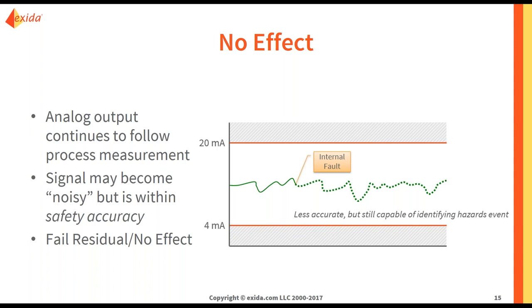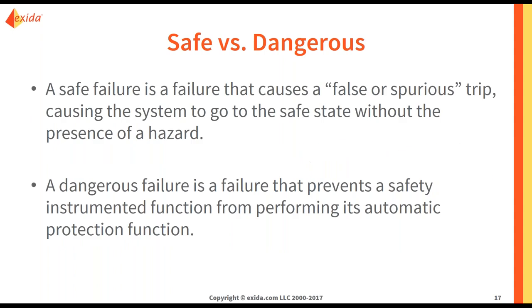So those are the different failure modes you might find with an analog transmitter. How do we classify them — how do we decide if they are safe, dangerous, detected, or undetected? A safe failure is a failure that causes a false or spurious trip, causing the system to go to the safe state without the presence of a hazard — a nuisance trip. A dangerous failure is a failure that prevents the SIF, or Safety Instrumented Function, from performing its automatic protective function, so it cannot respond to the hazard. There is no trip, but your SIF is no longer functional and you could have a dangerous event.